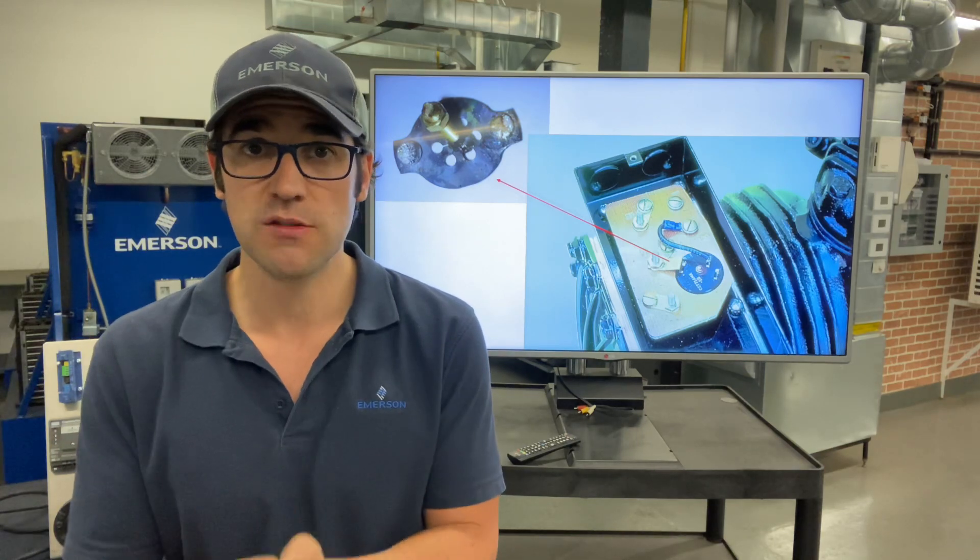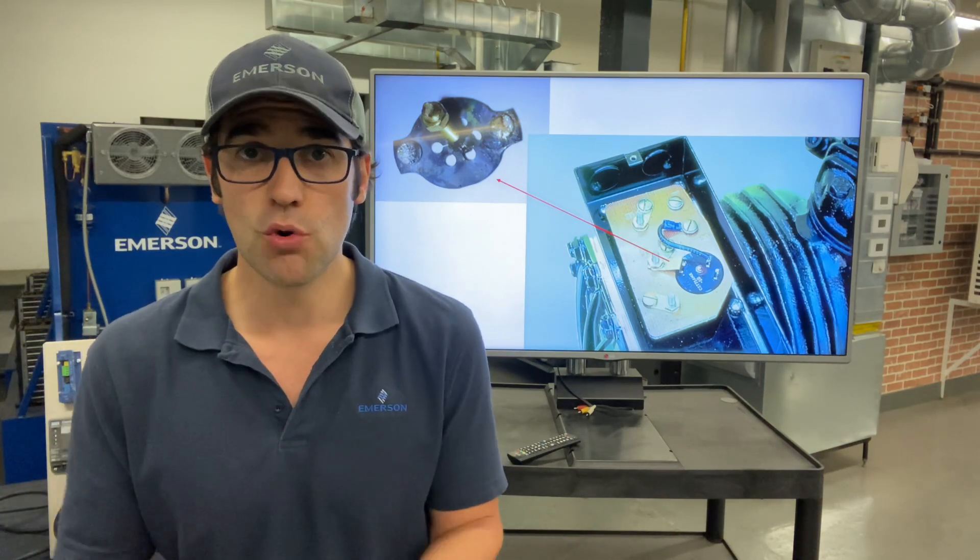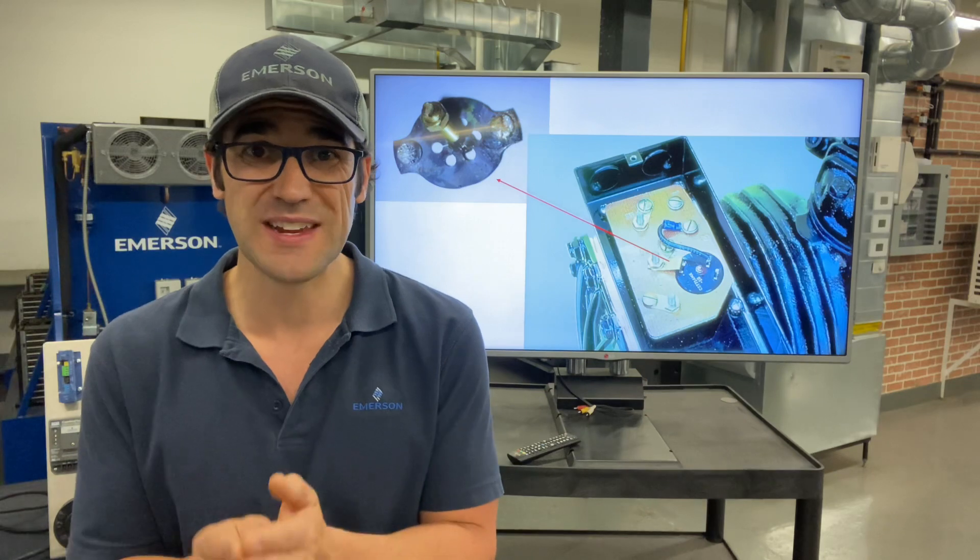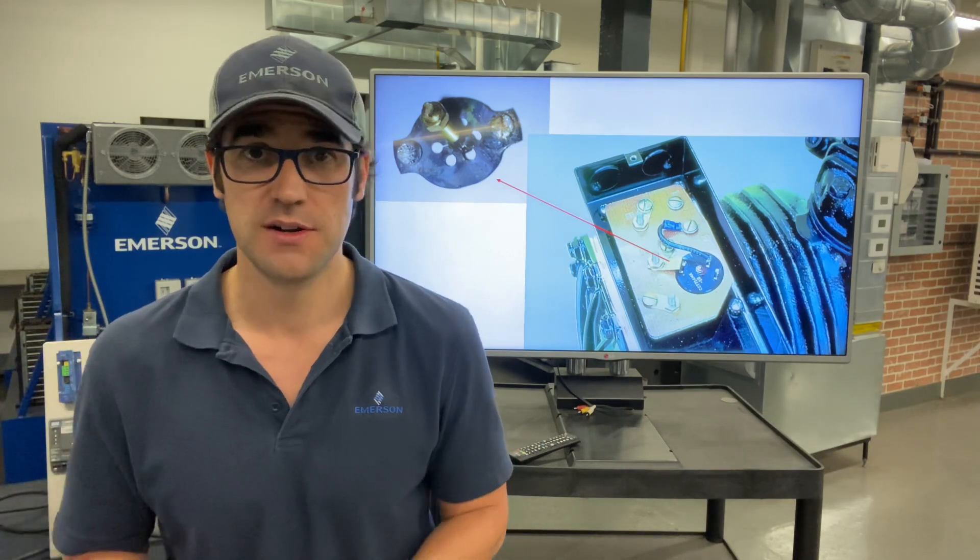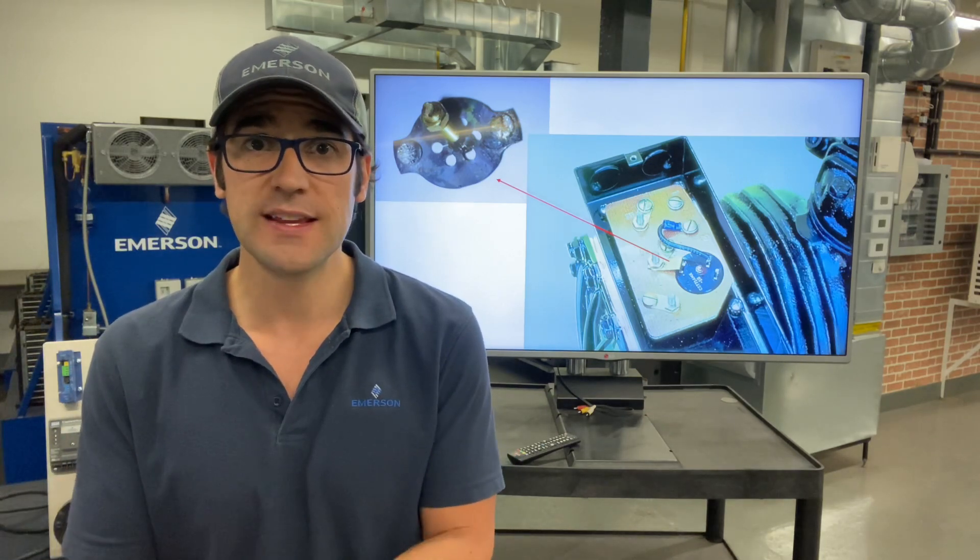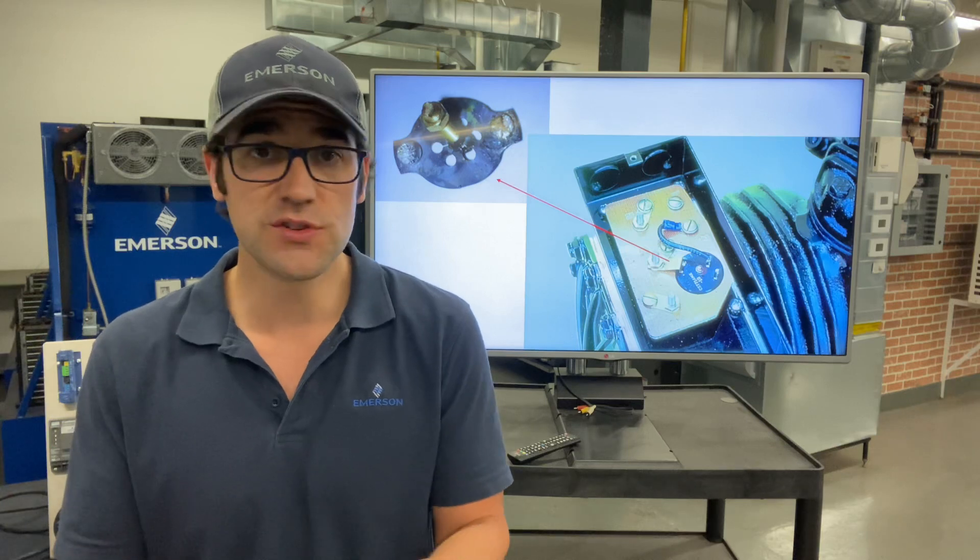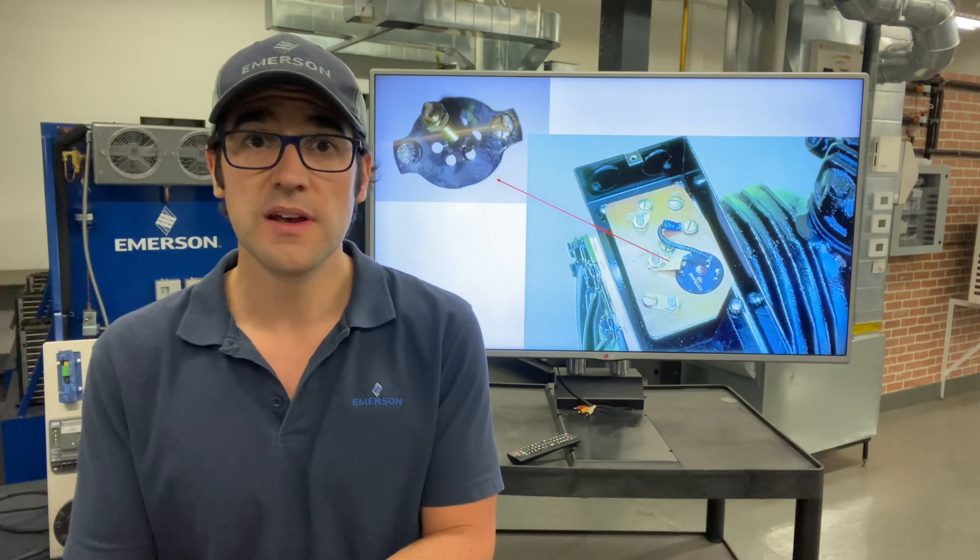The compressor is grounded but when he checked it with a high pot test the compressor is totally fine. This is a warranty compressor in the field less than a year and he said when he checked it mechanically it was good but he noticed some high temp.